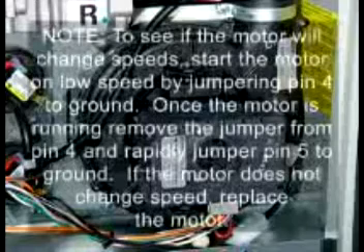Note: to see if the motor will change speeds, start the motor on low speed by jumpering pin 4 to ground. Once the motor is running, remove the jumper from pin 4 and rapidly jumper pin 5 to ground. If the motor does not change speed, replace the motor.